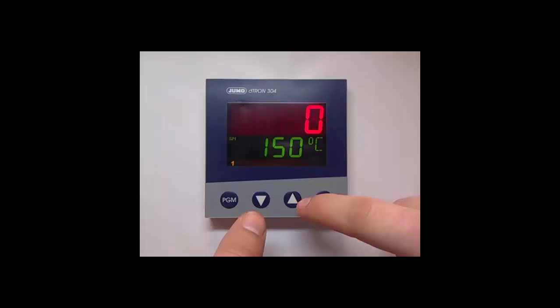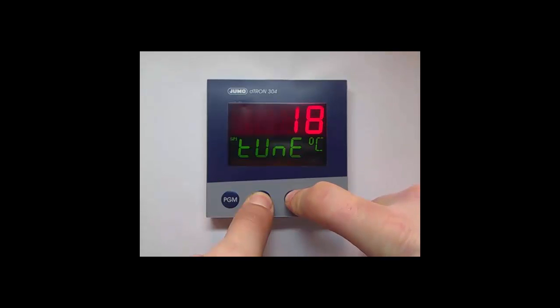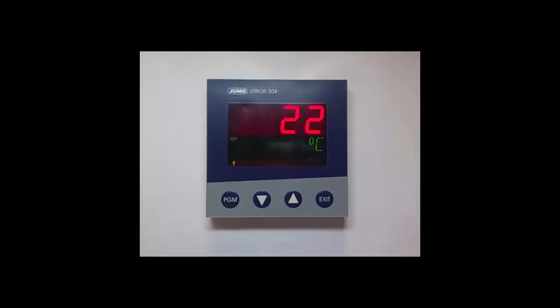But in most applications, PID action is required. The controller offers the possibility to find out control parameters with the auto-tuning function. After pressing the arrow keys up and down at the same time, auto-tuning is started. The controller switches the heater alternately on and off and produces the oscillation of the process value below the set point. After completing the auto-tuning functionality, the controller has found good control parameters for most plants. The parameters are stored in the first control parameter set.